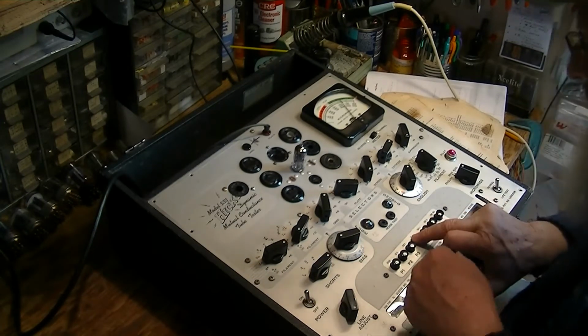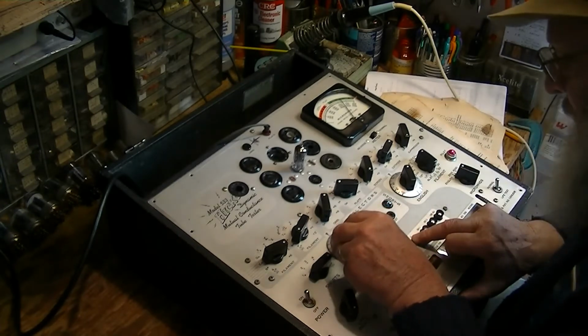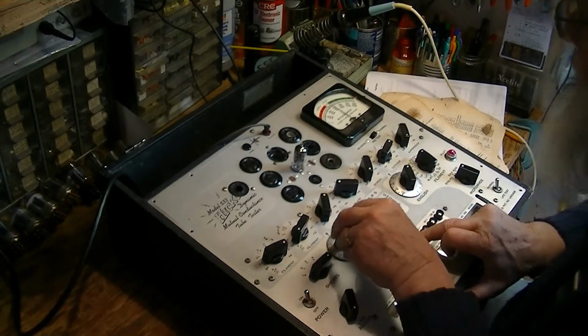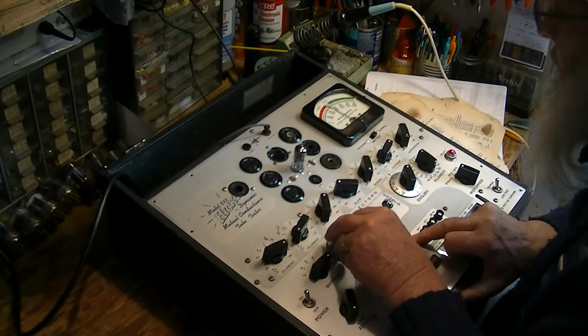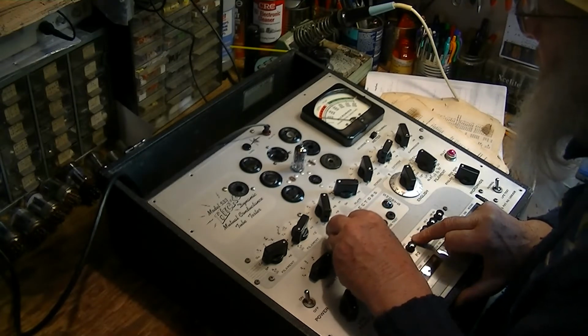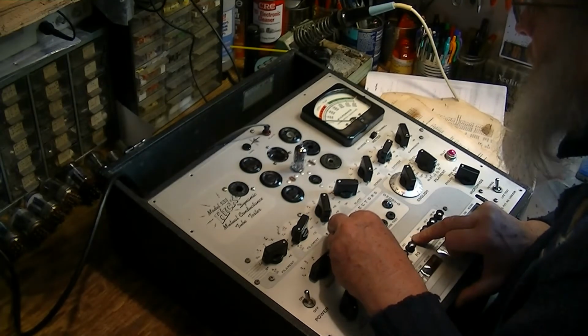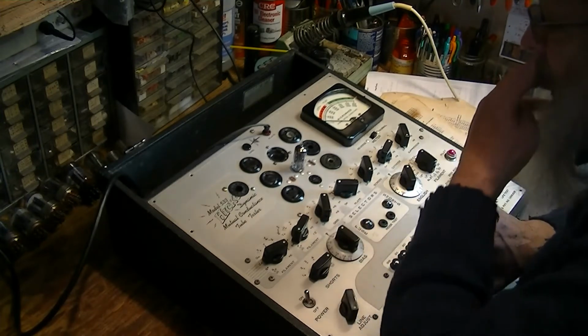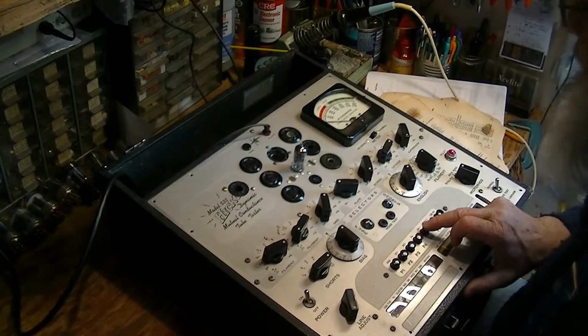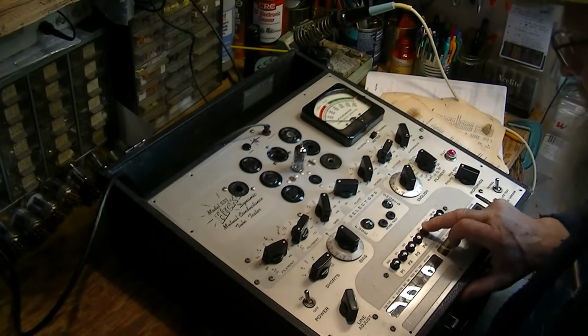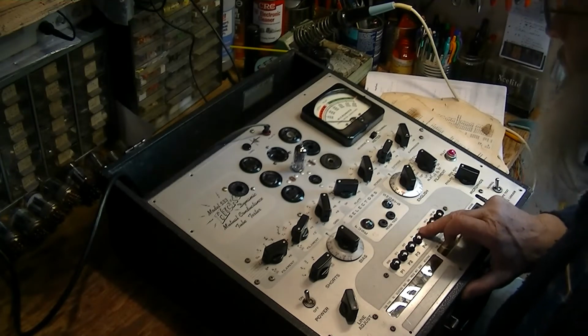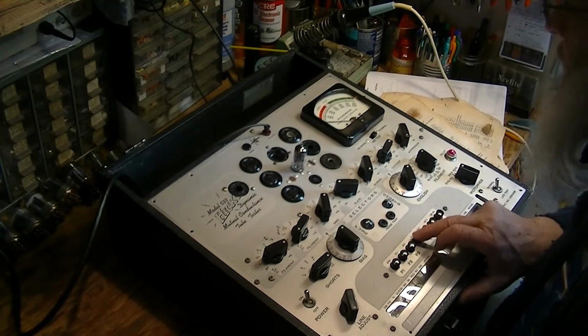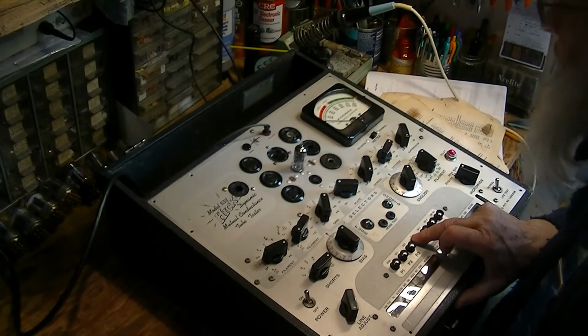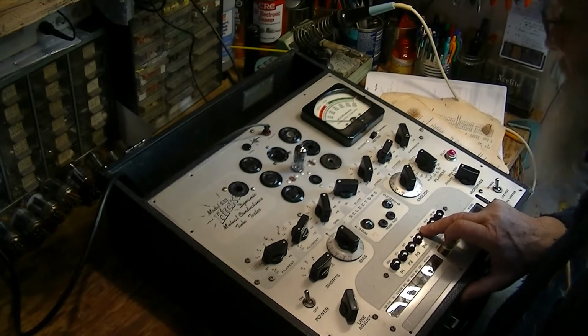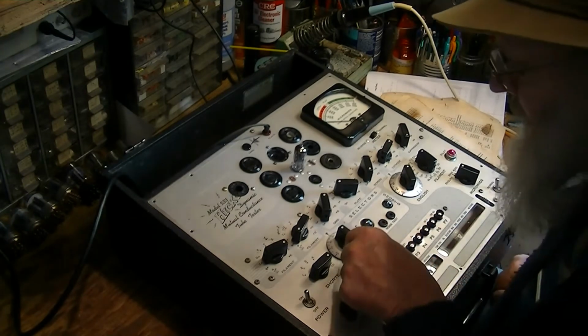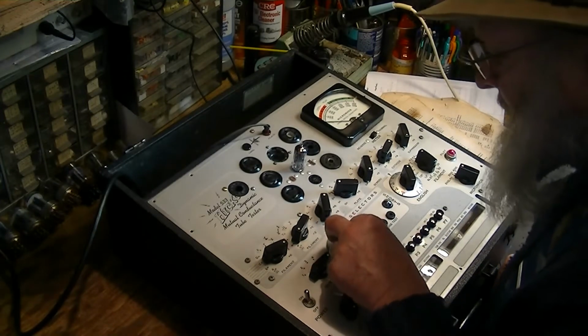And so what we do then is push the P4 test button and run the bias down until this is back down to about 100, the first big notch on the meter. Now we push the gas button, and it shouldn't come up higher than we set it at. Push the gas button and it still says 100, and that's good. So let's go back to the bias to 25.